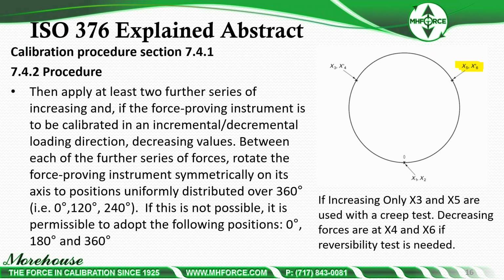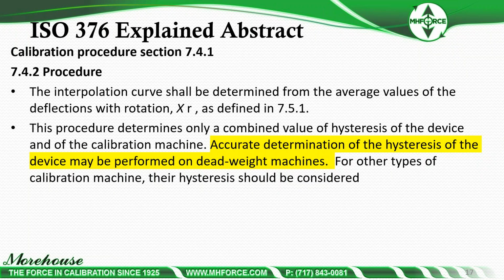If we're doing decremental loads and we're going to test for reversibility, we're going to do an increasing and decreasing load at X5 and X6, and we're going to do an increasing and decreasing load at X3 and X4. If we're doing increasing values only, we're just going to do X3 and X5. So the X4 and the X6 is for decreasing. And I'll show an example a little bit later on that with ascending calibration.